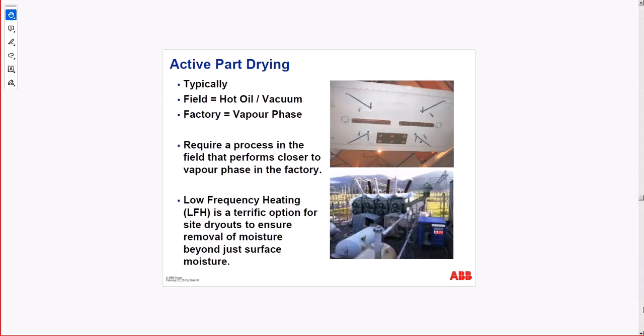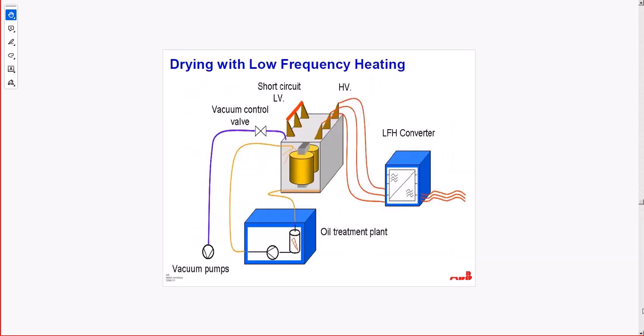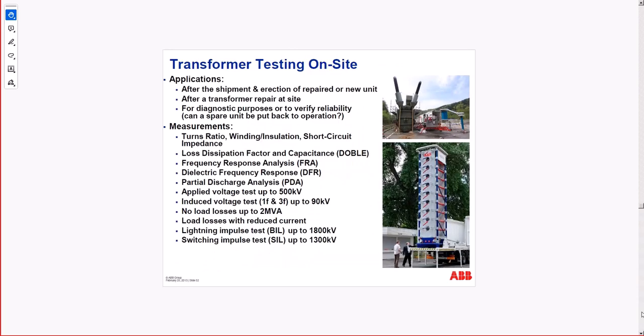Active part drying. So here is an example of drying out with low frequency heating. Drying with low frequency block diagram. The converter provides the power to the transformer, and then the vacuum pumps are also taking moisture out. Oil treatment plant at the same time. You recirculate the current, and yes, the transformer is offline because you have to supply this low frequency from the converter, not the real power. But the reconditioning of the oil can happen during normal operation. Actually, we will see the slides.